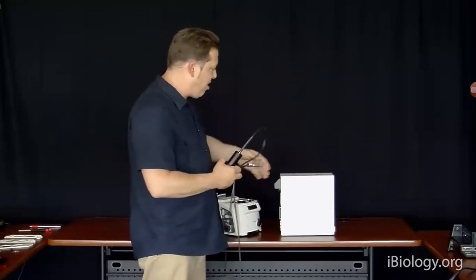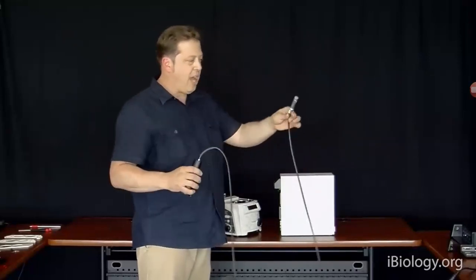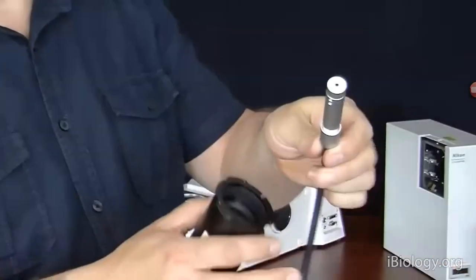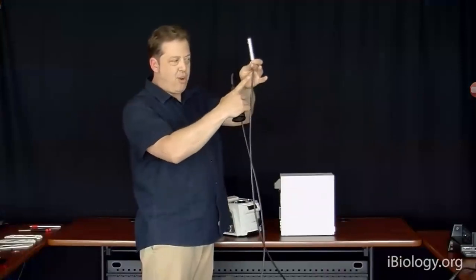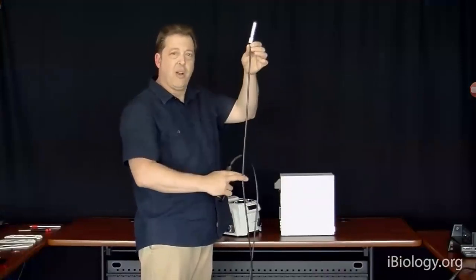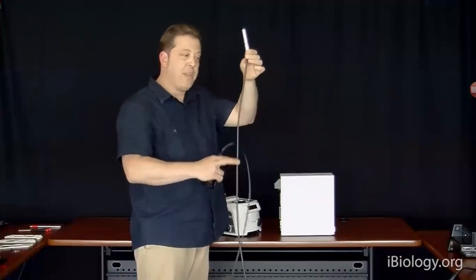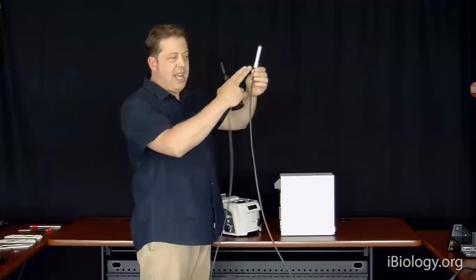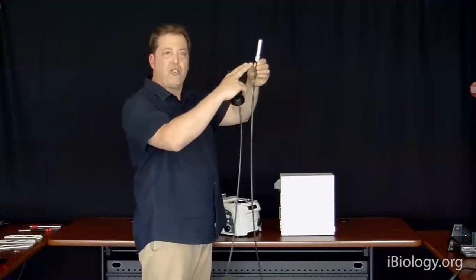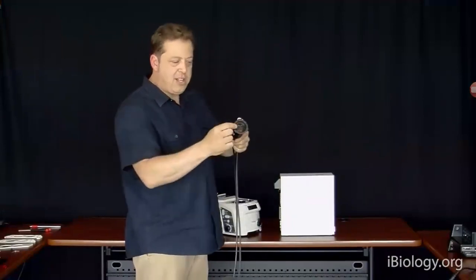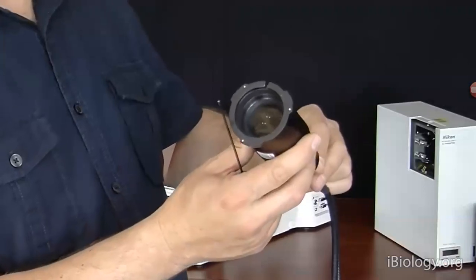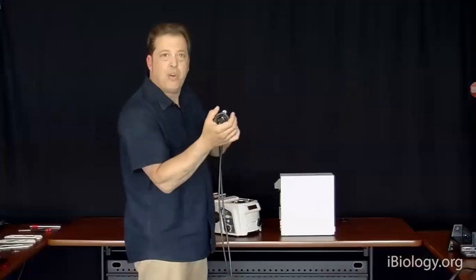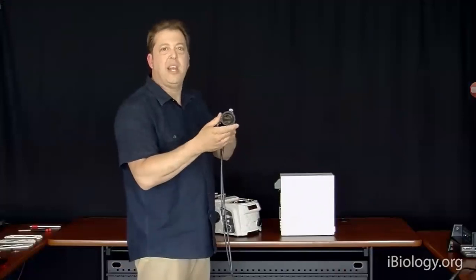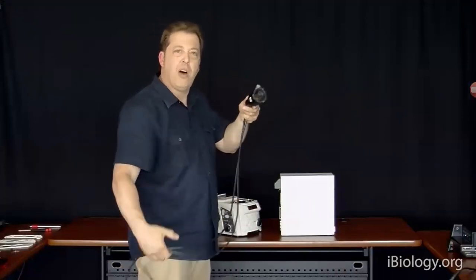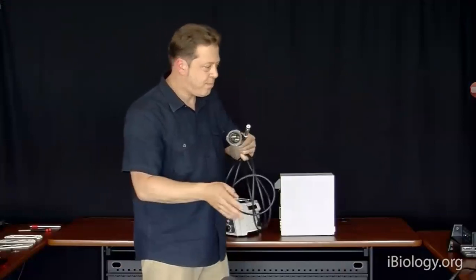This one is a metal halide system. We'll show you the bulb. And all the light goes in through what's called a liquid light guide. So the light coming into this aperture is actually trapped through total internal reflection in a core filled with liquid. I believe in this case it's water that would keep the light based on total internal reflection within that core of water, into this collimating lens, which is matched to the optics in the microscope and puts a large collimated beam of light into the microscope for epifluorescence illumination.